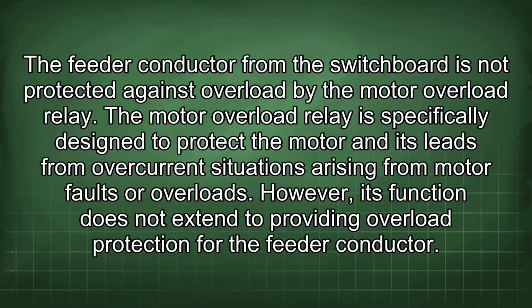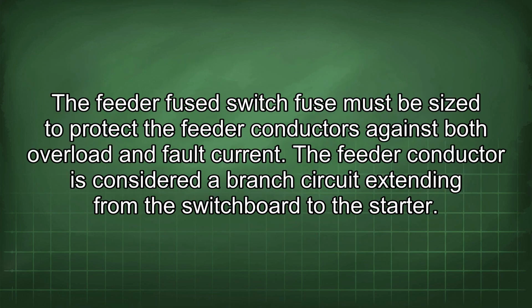The feeder conductor from the switchboard is not protected against overload by the motor overload relay. The motor overload relay is specifically designed to protect the motor and its leads from overcurrent situations arising from motor faults or overloads. However, its function does not extend to providing overload protection for the feeder conductor. The feeder fused switch fuse must be sized to protect the feeder conductors against both overload and fault current.